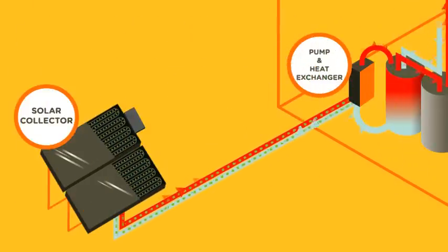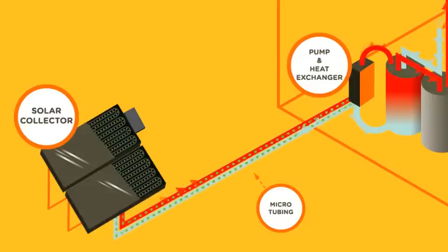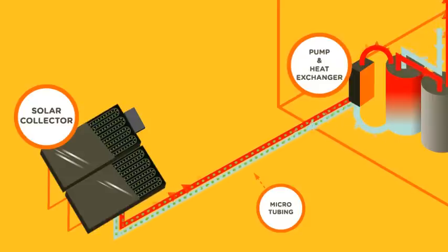The Sunward solar collectors and Sunward heat exchanger are connected by pre-insulated Sunward microtubing. These are 3/8 inch flexible copper lines and are insulated. For direct burial we have the Sunward easy bury microtubing which is our microtubing encased in 3 inch flexible black conduit.